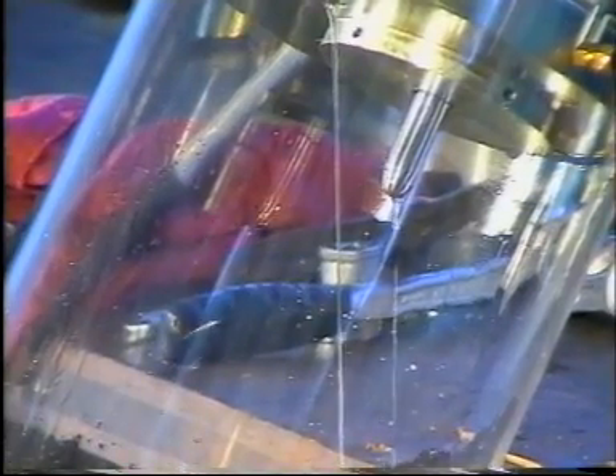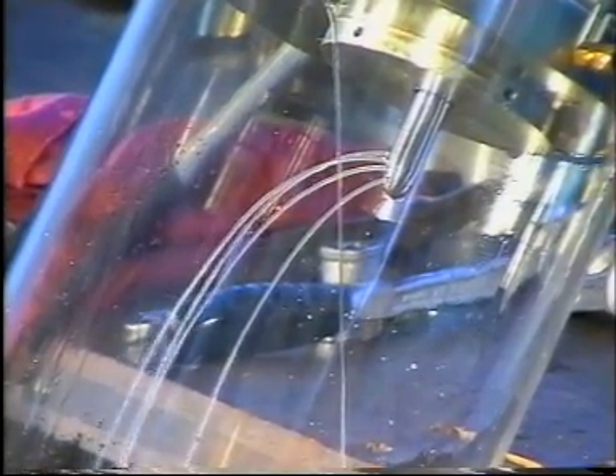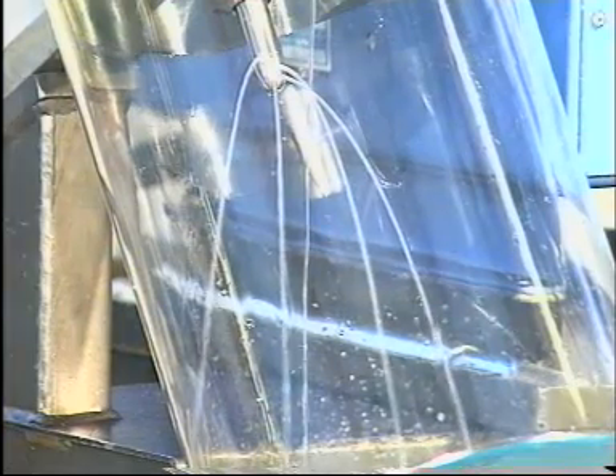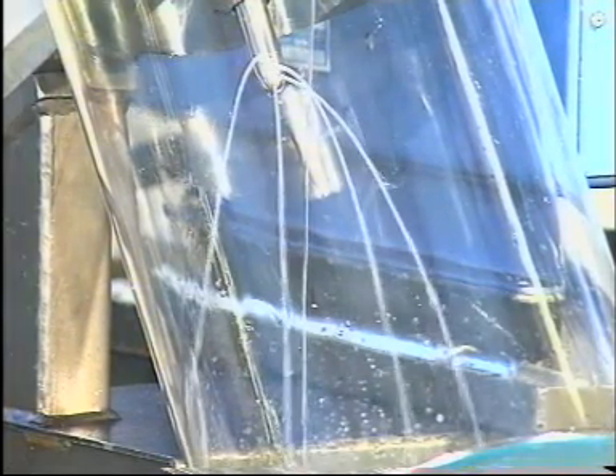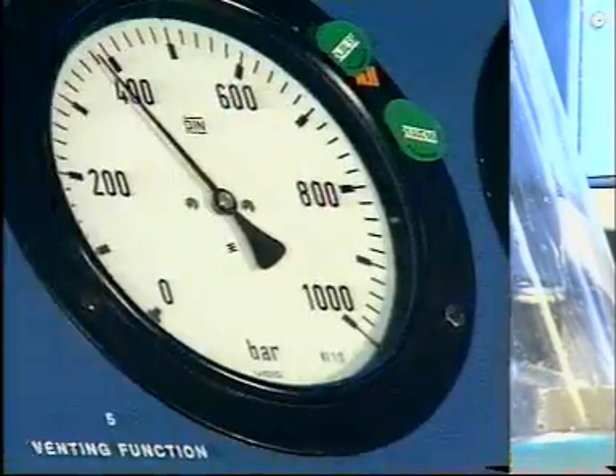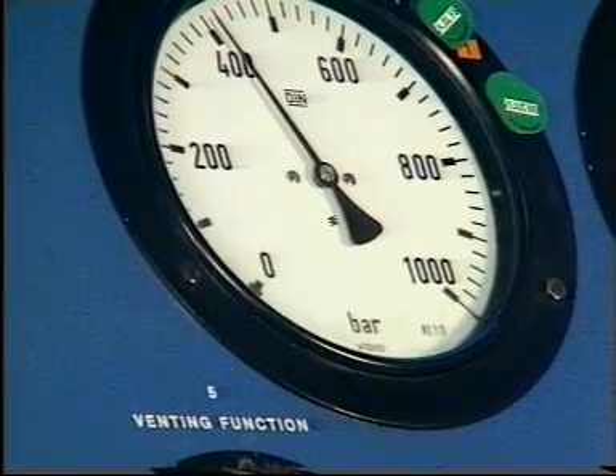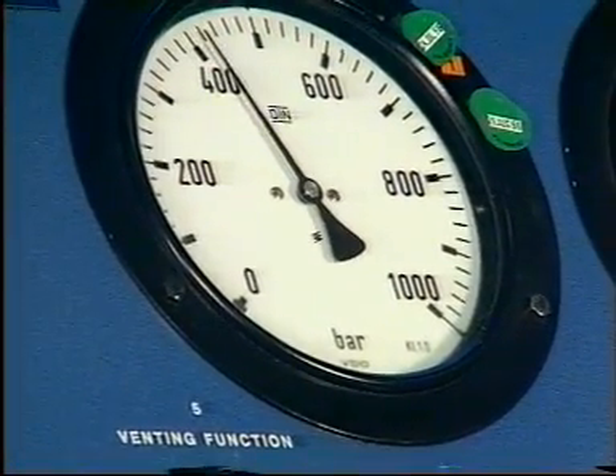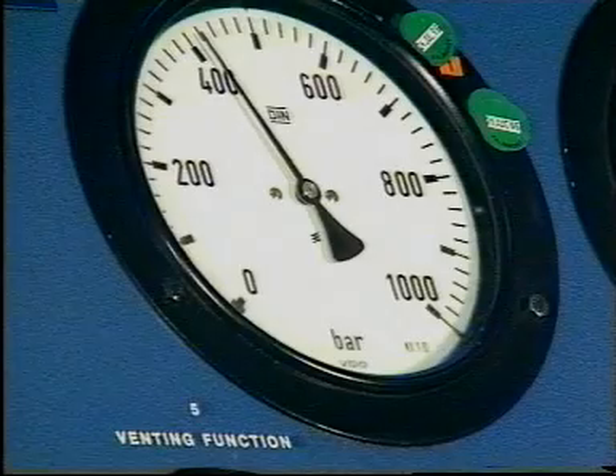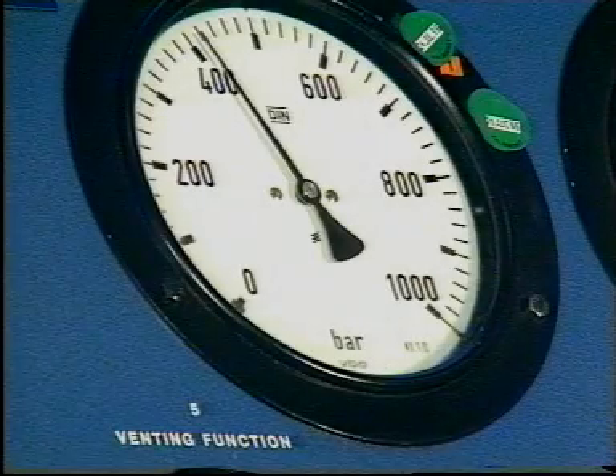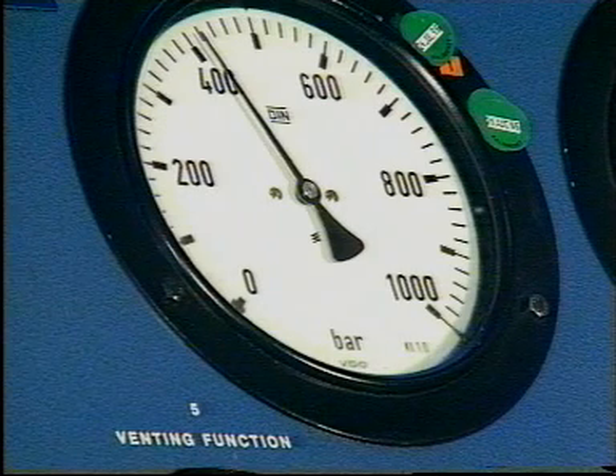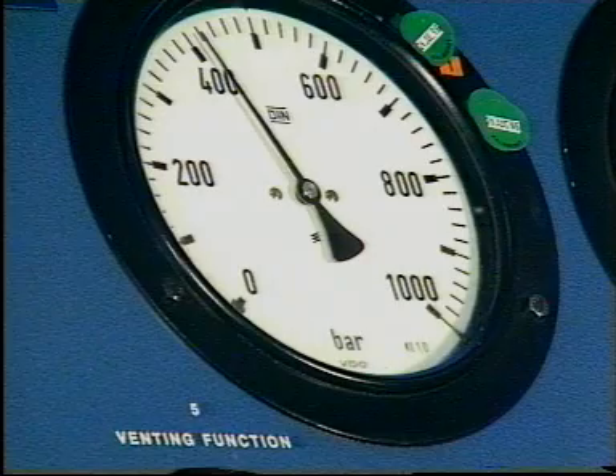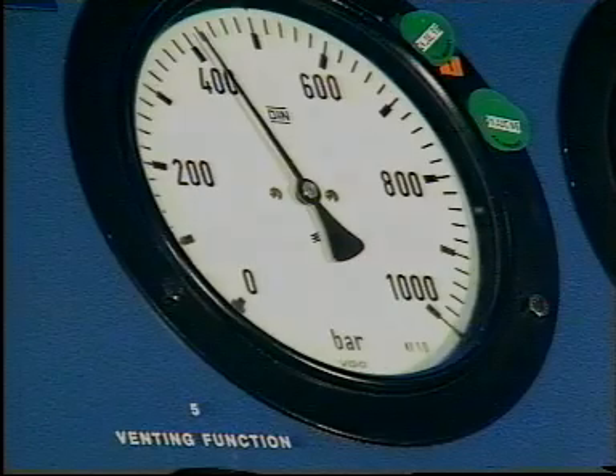Slowly increase the pressure until fuel oil is emitted from all the atomizer holes. Read the actual opening pressure on the pressure gauge marked opening pressure. Compare the actual opening pressure with the pressure specified in the Instruction Book, Volume 2, Chapter 909, and, if necessary, adjust the pressure by inserting or removing discs.